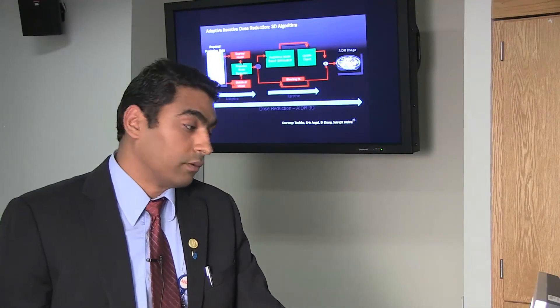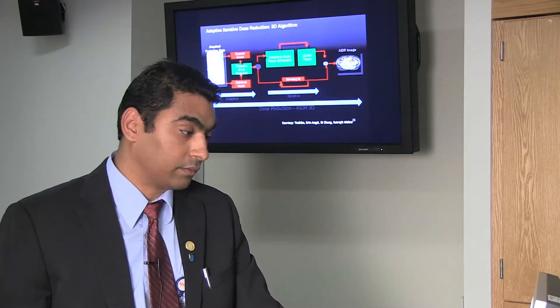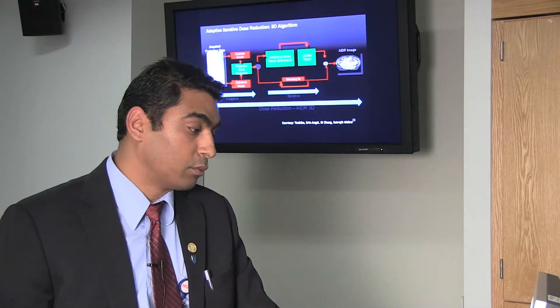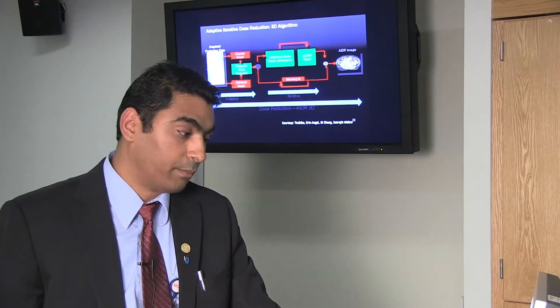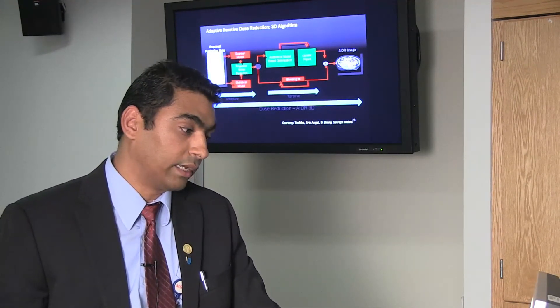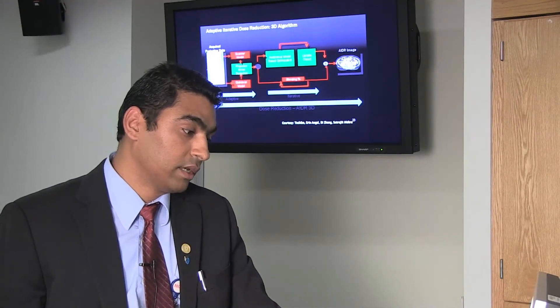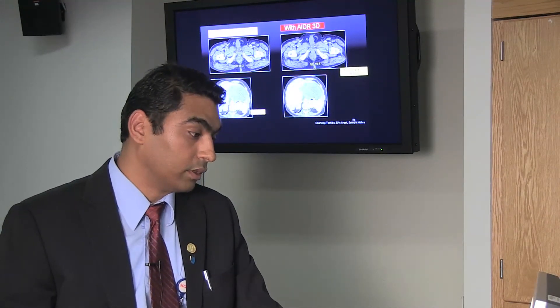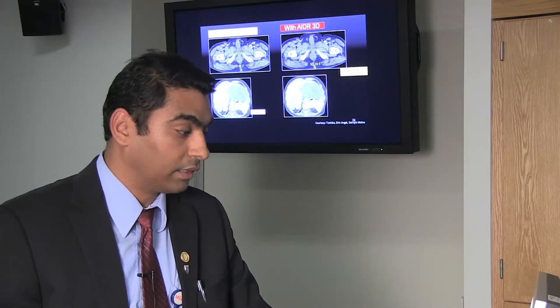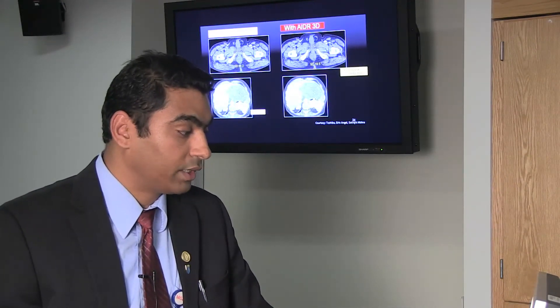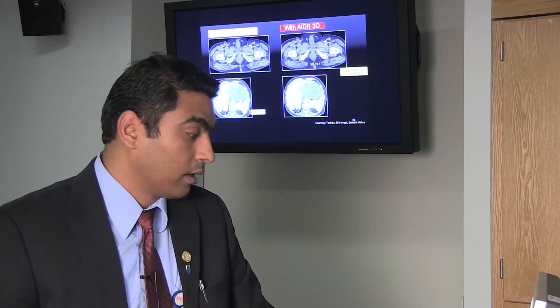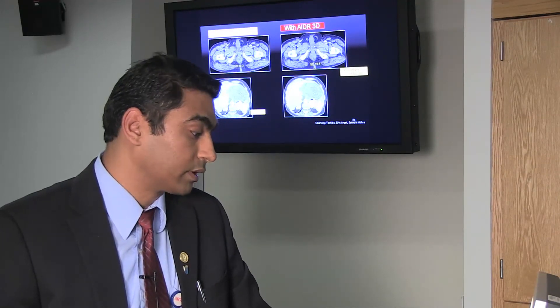Toshiba has the adaptive iterative dose reduction, AIDR. This algorithm starts from projection data, incorporates scanner model information and a statistical model, updates the raw data, then goes to image space where it applies anatomical model-based optimization with a blending tool to generate final AIDR images. In an example, without AIDR there are many streaks and noise in the pelvic region; with the AIDR 3D algorithm, image noise goes down. In the liver parenchyma scanned at roughly 2.5 mSv, image noise in the liver has gone down.